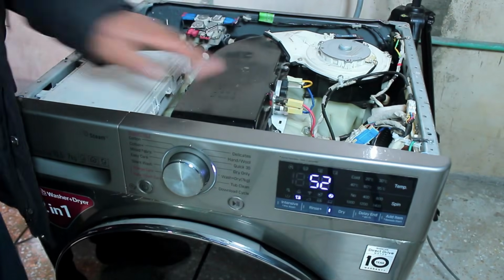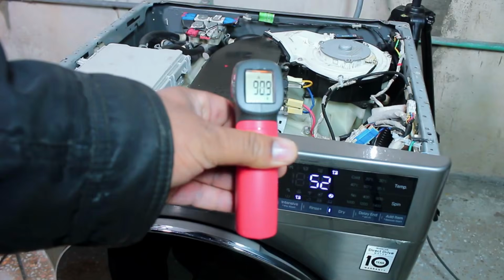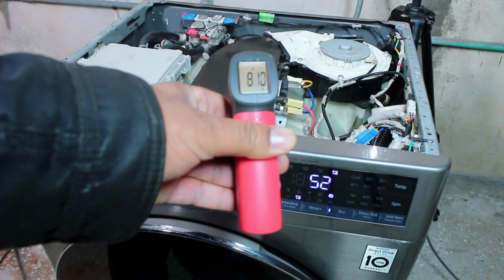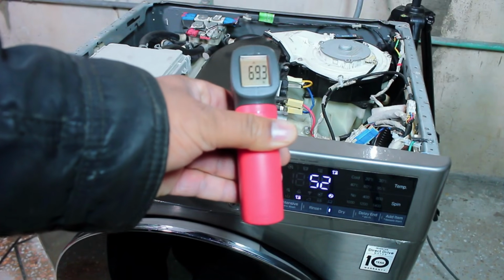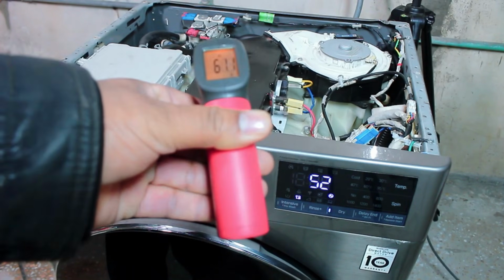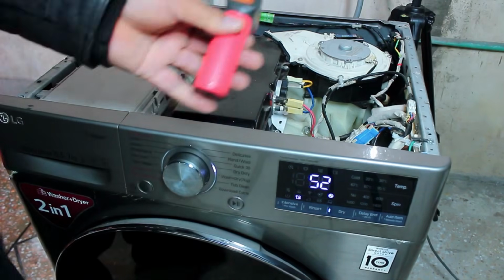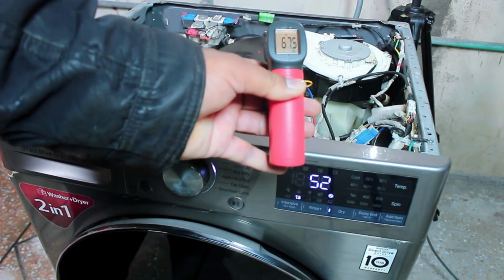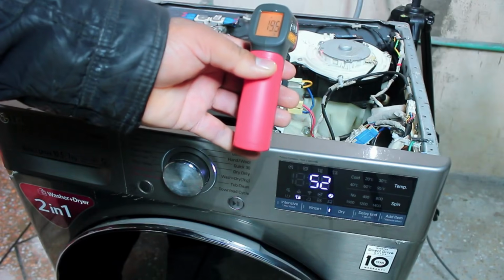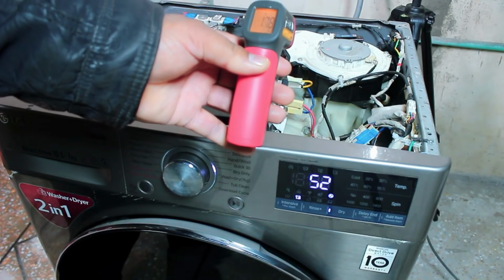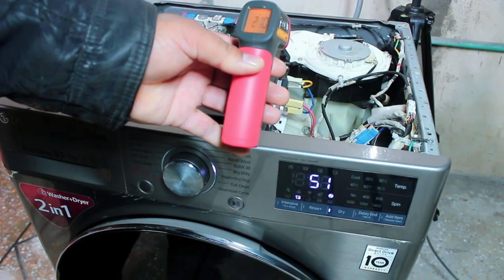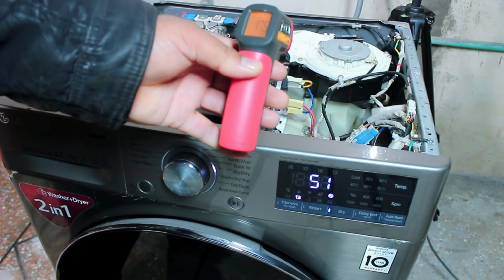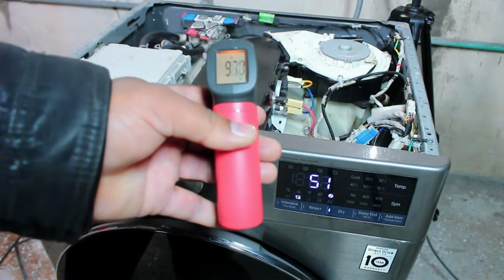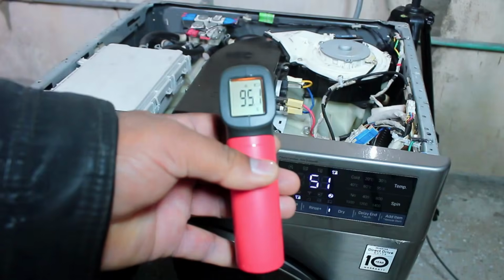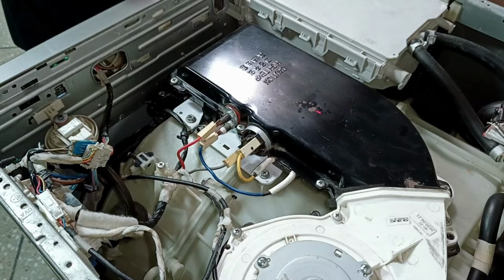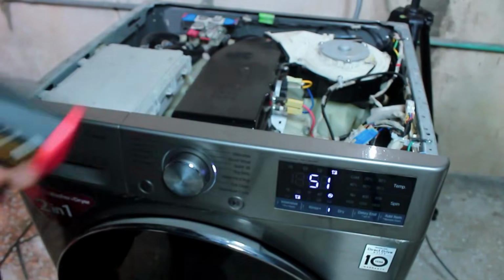Now when I touch this area, it has become quite hot. So I will check the temperature here. As you can see, it is showing around 80 to 88 degrees here. A little further ahead, it is around 60 degrees. Now as I check at the back side, it shows 75 degrees, then 58 degrees. Near the motor, it is showing 19 degrees, which means the motor is completely cool and there is no issue with it. Meanwhile, near the heating element, the temperature has gone up to 90 to 95 degrees, even reaching 98 to 100 degrees. So it is getting quite hot.